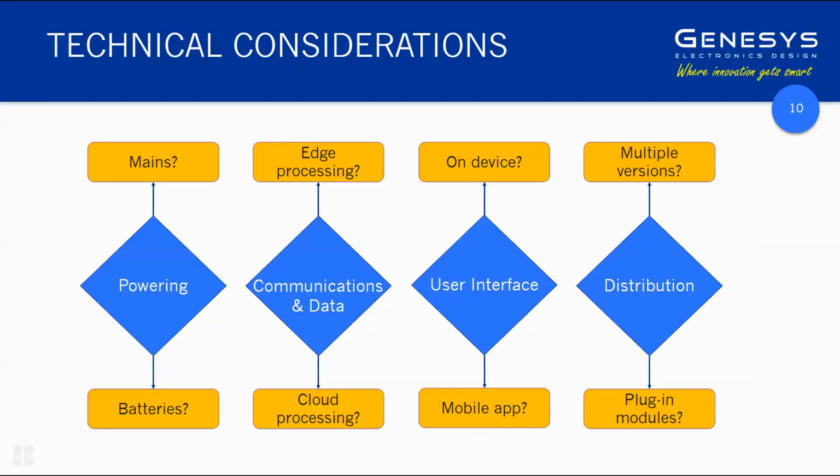Okay, so just to give you a sense of some of the particular considerations that relate to active devices, obviously you have got a basic choice there about how you're going to power it, via batteries or mains. And there are good reasons for that, particularly relating to safety and how you might be able to isolate a patient from electrical shock or dangers. Any comments on that, Jeff?